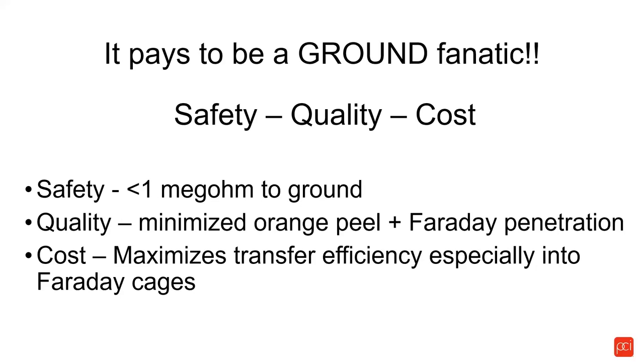We check megaohms using a megaohmmeter. From a quality point of view, a good ground assures you of minimized orange peel and improved Faraday cage penetration — two of the biggest issues you face as a coater on a daily basis. From a cost point of view, a good quality ground maximizes transfer efficiency. In other words, you're going to put more powder on your part with a good ground than with a poor ground — and that's actually demonstrable.